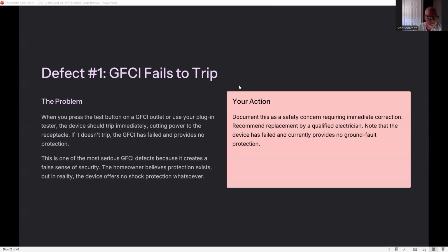Defect number 1, GFCI fails to trip. The problem: when you press the test button on a GFCI outlet or use your plug-in tester, the device should trip immediately, cutting power to the receptacle. If it does not trip, the GFCI has failed and provides no protection. This is one of the most serious GFCI defects because it creates a false sense of security. The homeowner believes protection exists, but in reality, the device offers no shock protection whatsoever.